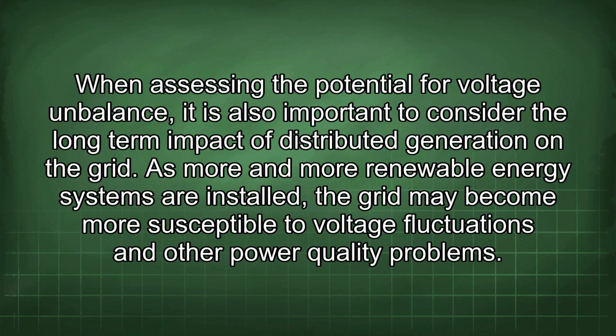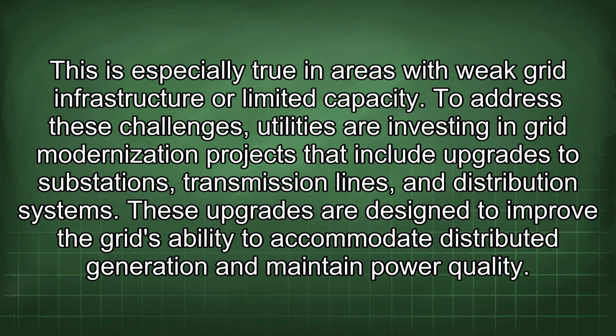When assessing the potential for voltage imbalance, it is also important to consider the long-term impact of distributed generation on the grid. As more and more renewable energy systems are installed, the grid may become more susceptible to voltage fluctuations and other power quality problems. This is especially true in areas with weak grid infrastructure or limited capacity. To address these challenges, utilities are investing in grid modernization projects that include upgrades to substations, transmission lines, and distribution systems. These upgrades are designed to improve the grid's ability to accommodate distributed generation and maintain power quality.